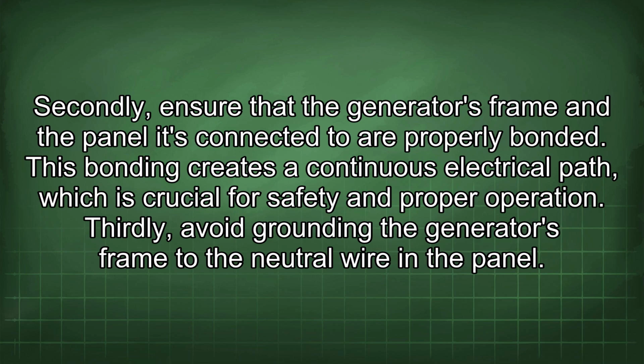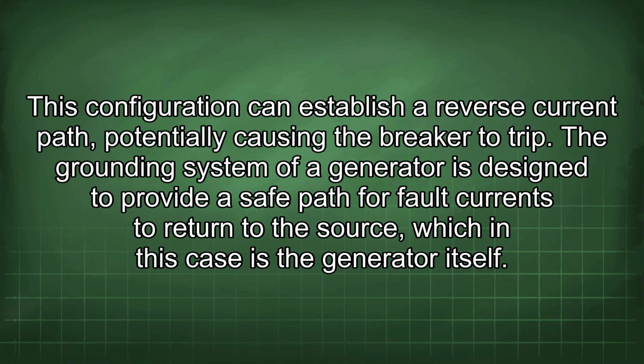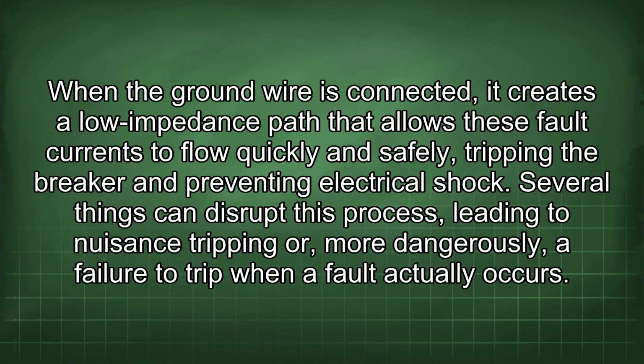Thirdly, avoid grounding the generator's frame to the neutral wire in the panel. This configuration can establish a reverse current path, potentially causing the breaker to trip. The grounding system of a generator is designed to provide a safe path for fault currents to return to the source, which in this case is the generator itself. When the ground wire is connected, it creates a low impedance path that allows these fault currents to flow quickly and safely, tripping the breaker and preventing electrical shock.